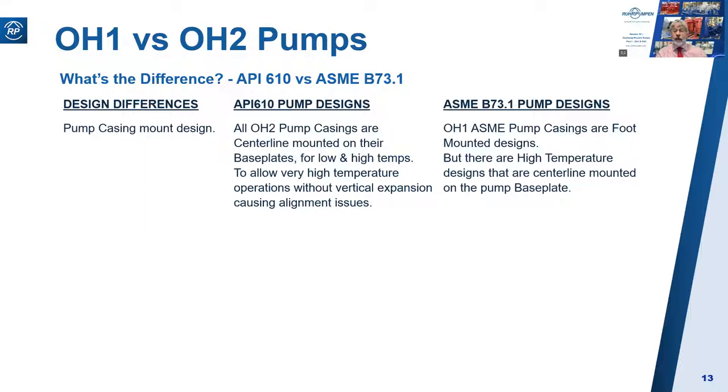Whereas ANSI pumps are designed for ambient or lowish temperatures, so the expansion in a vertical direction is not significant. If you try to use that in a hot service, you would very quickly end up with alignment problems and mechanical seals leaking.